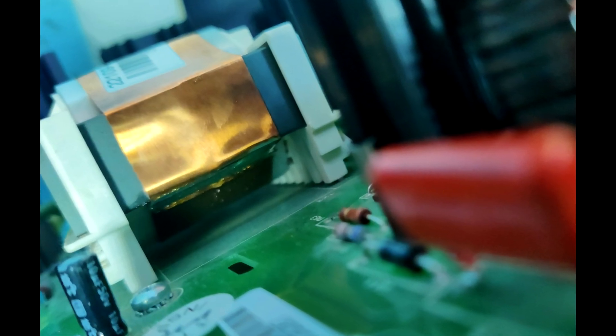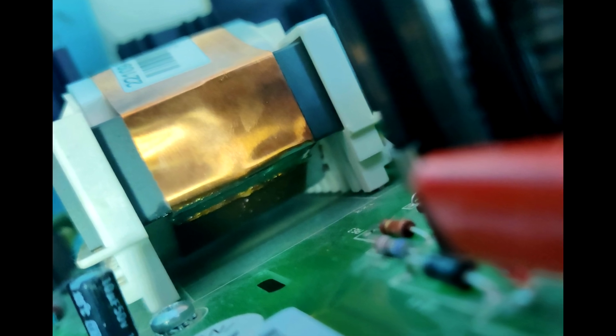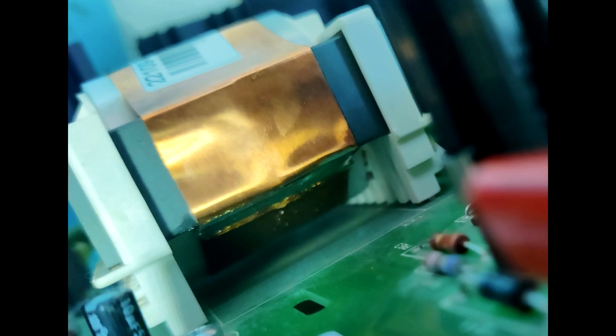Now if you want to implement such a measure in your design, so to add a flux band to your transformer, there are a few things to mention about this. So on the one side, the flux band is a band of conductive material, so copper usually. And it's an unisolated structure. So there's no isolation on top of it, you have exposed conductive copper. And especially at transformers running at high voltages, this raises safety issues. So you need to take into account your clearance and creepage distances when applying this sort of measure. That's why commonly you won't see flux bands that are extremely wide. So there is a lot of space, but they won't fill up all the space. Rather they will be much thinner. And this is done to ensure the safety distances between the flux band and the primary and secondary side. So you don't have some sort of arcing or any sort of hazards.